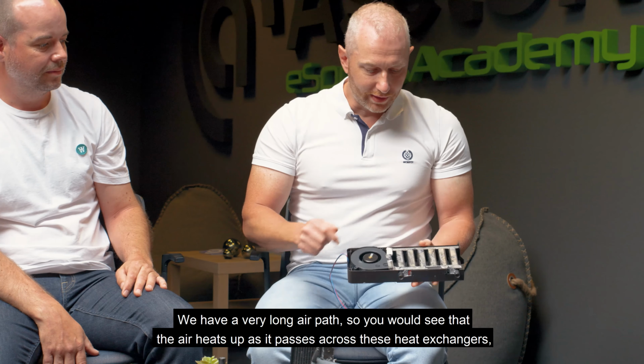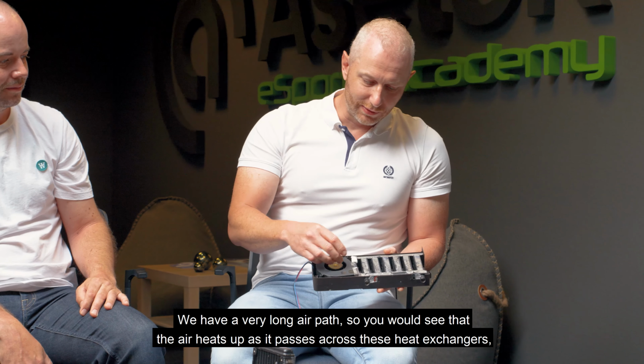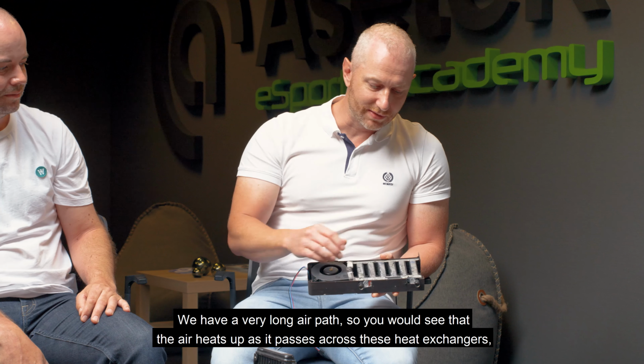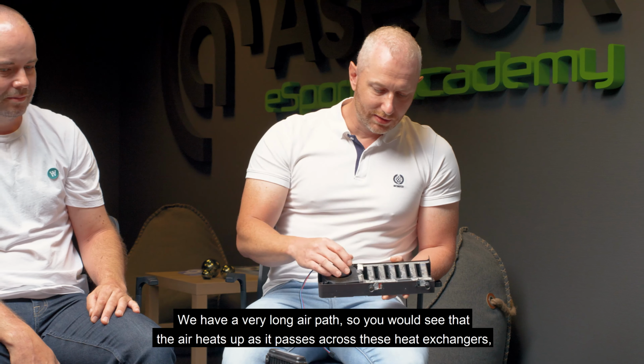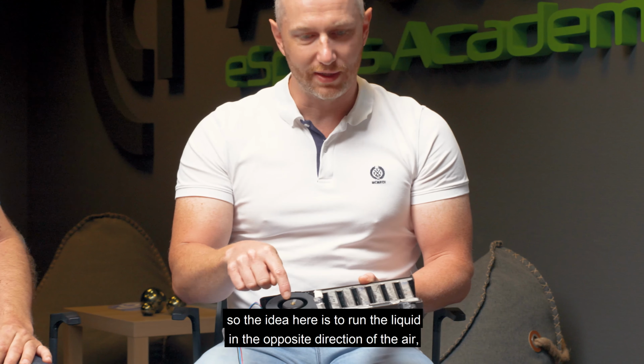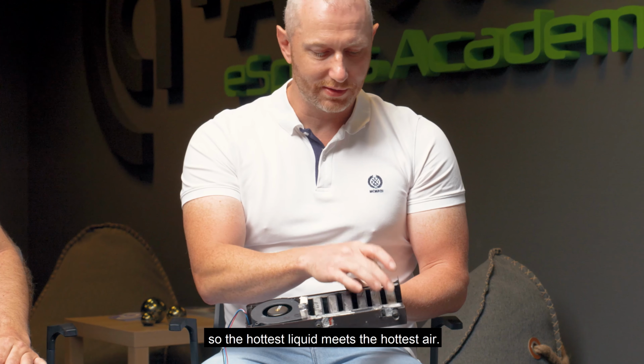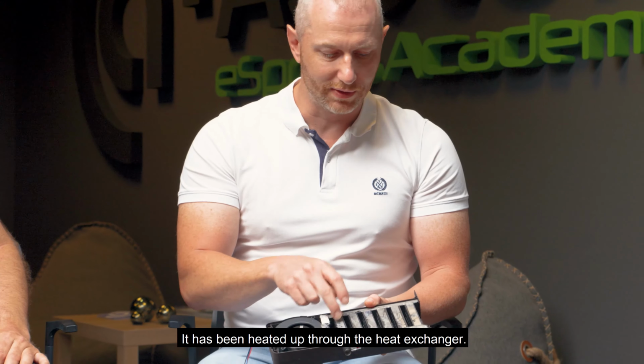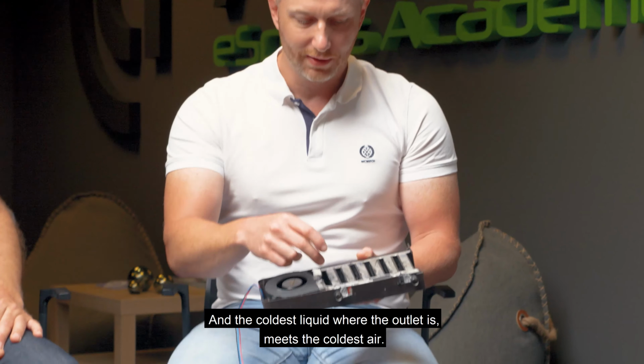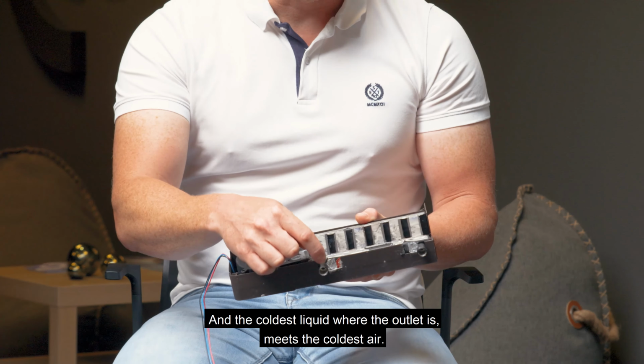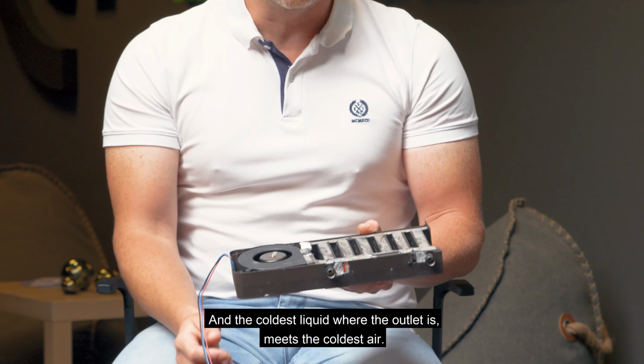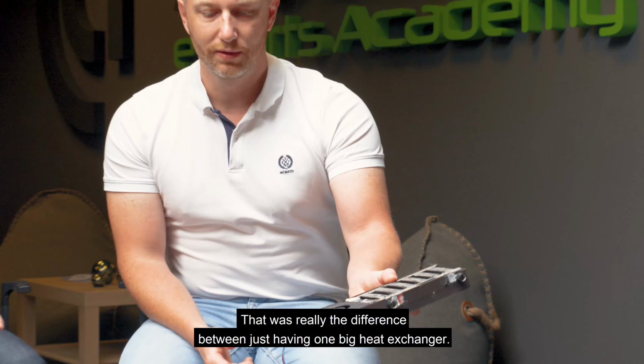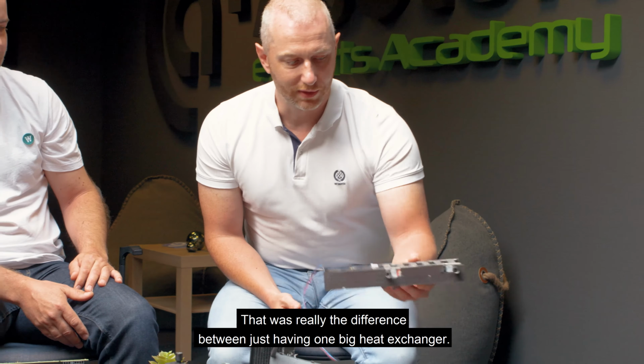You have a very long air path, so you would see that the air heats up as it passes across these heat exchangers. So the idea here is to run the liquid in the opposite direction of the air. So the hottest liquid meets the hottest air, which has been heated up through the heat exchanger, and the coldest liquid, where the outlet is, meets the coldest air. So that was really the difference between this and just having one big heat exchanger.